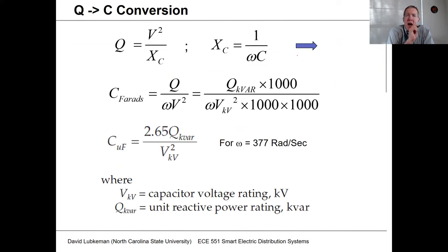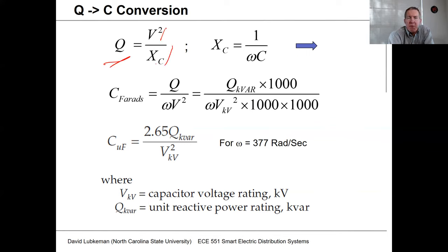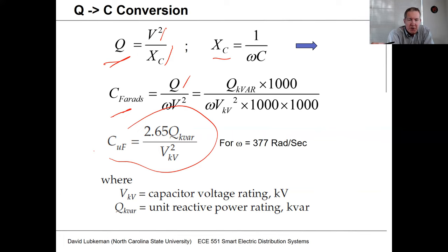We can convert between Q and capacitance. For utility capacitors, we typically don't talk about them in terms of microfarads — we talk about them in terms of the amount of reactive power they generate at their nominal rated voltage. Since Q equals V-squared divided by capacitive reactance, and capacitive reactance is 1 over omega-C, you can relate C to Q, which will be a value in microfarads generally.